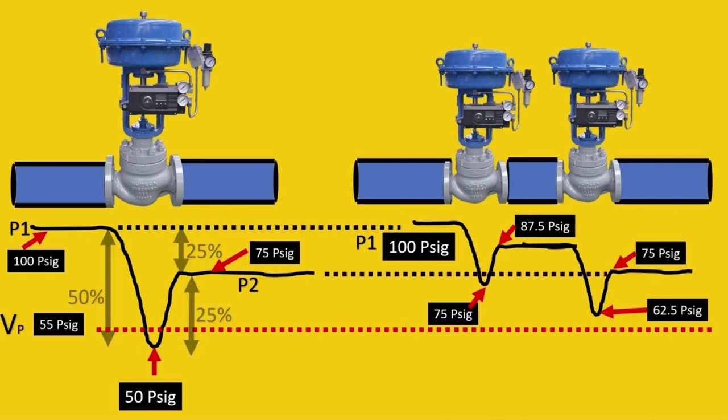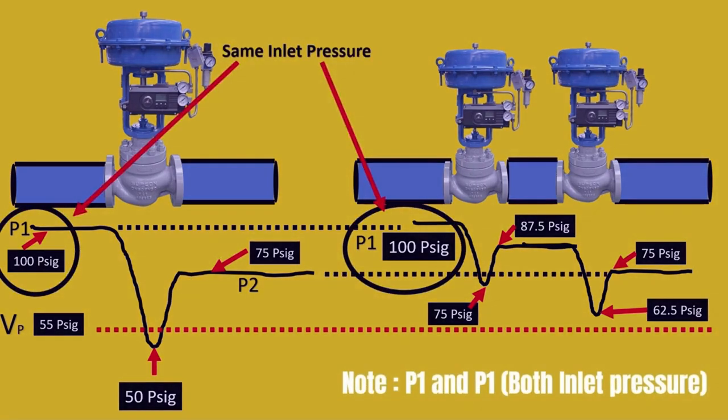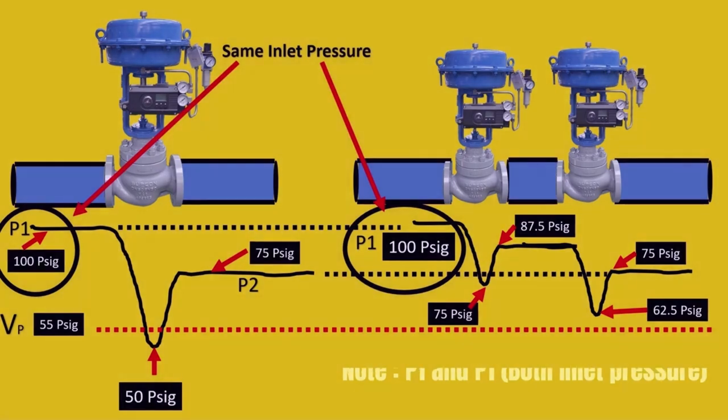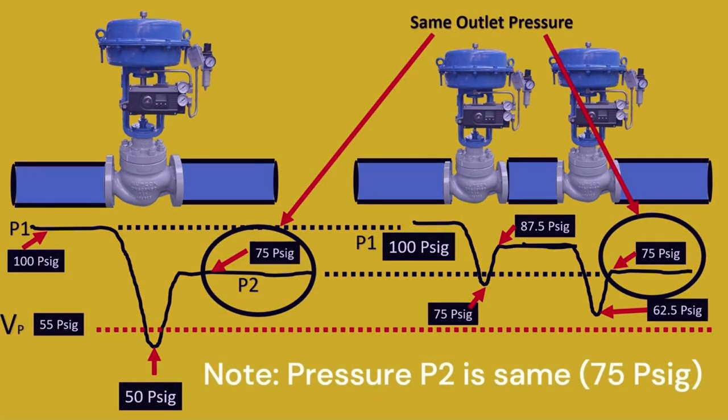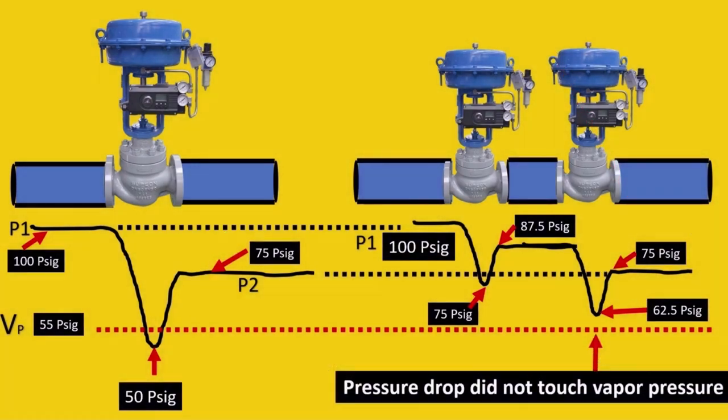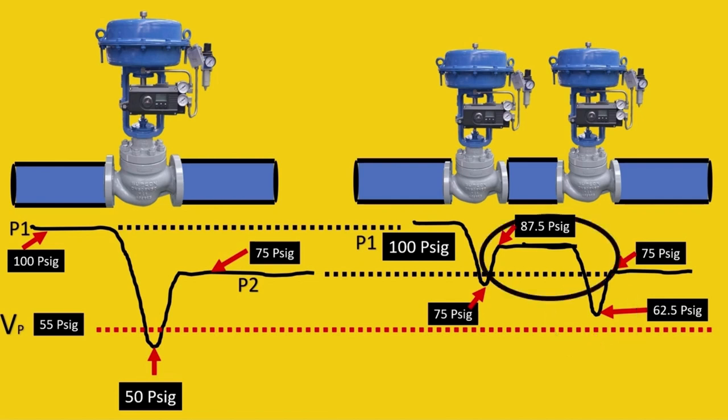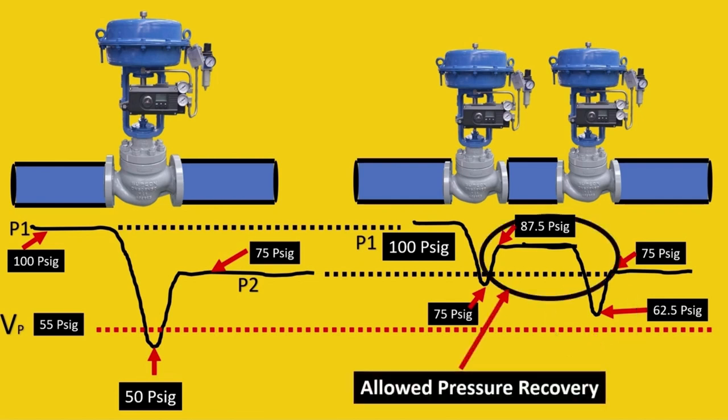If you notice, P1 and P2 are the same in both cases - 100 psig inlet and 75 psig outlet. However, the pressure curve in the second case did not touch the vapor pressure, so cavitation did not happen. This is because of giving time for pressure recovery to happen.